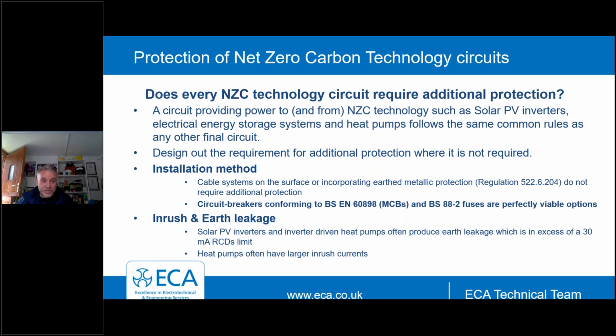A lot of manufacturers are stating that where you do need to use an RCD for additional protection, it should be a type B or a type F. It might be 20 to 30 pounds for a type A. It might be 200 to 300 pounds for a type B or F. So there's huge differences here, where an MCB or circuit breaker will provide the protection you need without the use of an RCD.